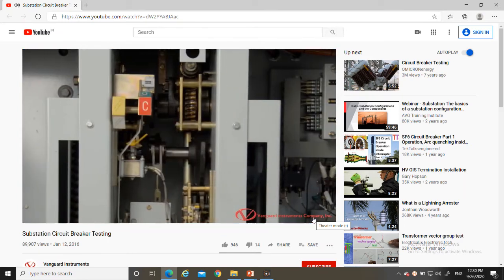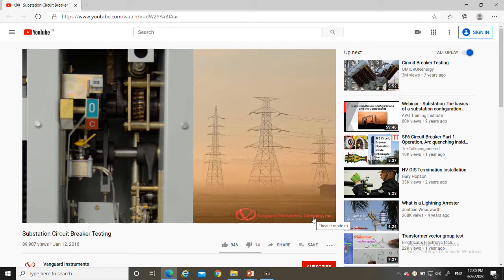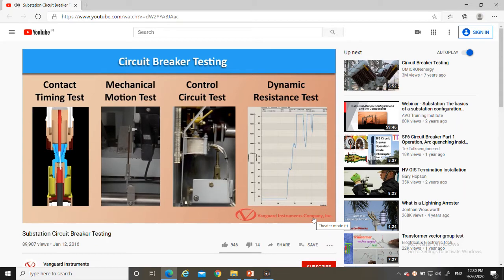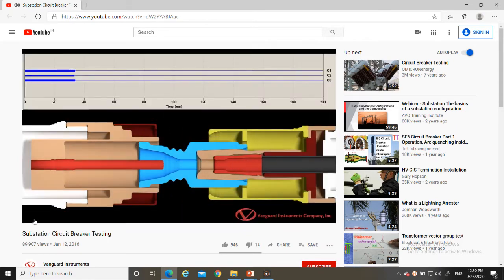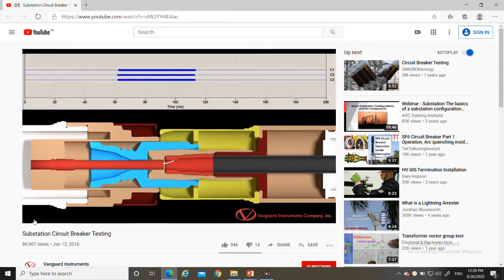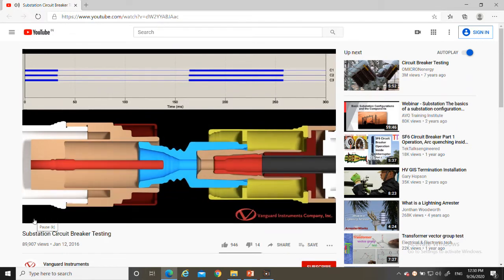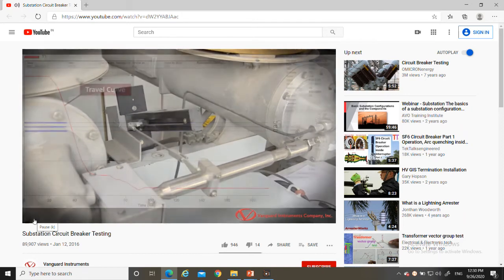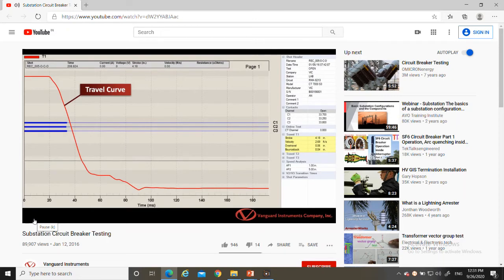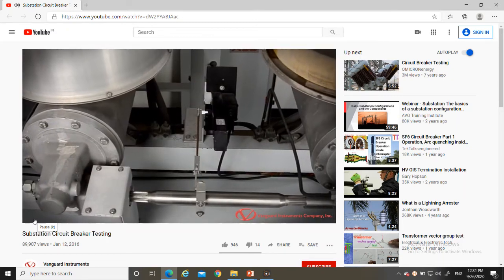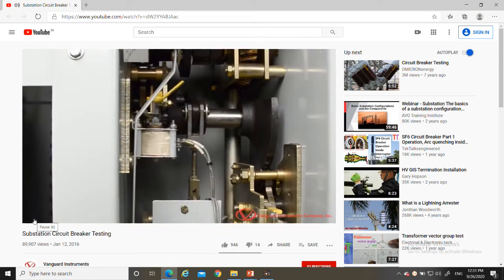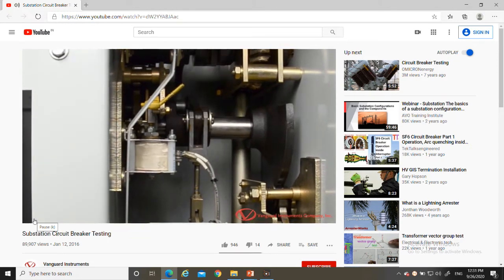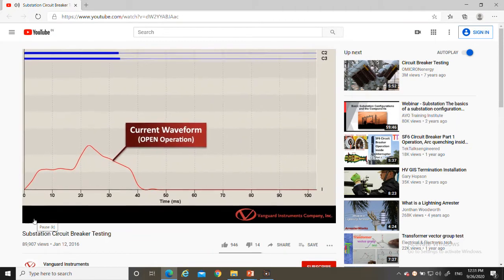Regardless of type, it is very important to test circuit breakers regularly. Regular testing can ascertain proper breaker operation in case of system fault and can improve system reliability. Contact timing tests compare the breaker's main and resistor contact performance against manufacturer's specifications — open, close, open, close, close-open, and open-close-open operations are timed in milliseconds and cycles. Motion tests with a transducer check mechanism stroke, velocity, damping, and over travel. A breaker's control circuit can also be tested by measuring trip and close coil current and minimum pickup voltage.